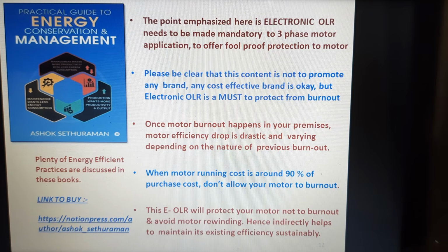Once a motor burnout happens in your industry premises, the motor efficiency also drops drastically, and it is a varying drop of efficiency depending on the nature of the previous motor burnout. When the motor running cost is more than 90% of the purchase cost, don't allow your motor to burn out. This electronic OLR will protect your motor from burning out and avoid repeated motor rewinding. Hence, it indirectly helps to maintain the existing motor efficiency sustainably.